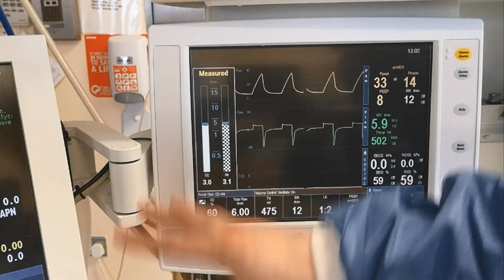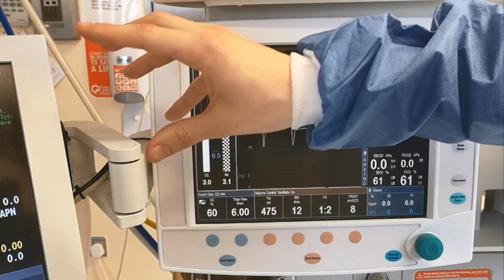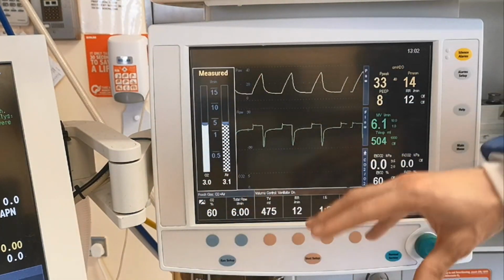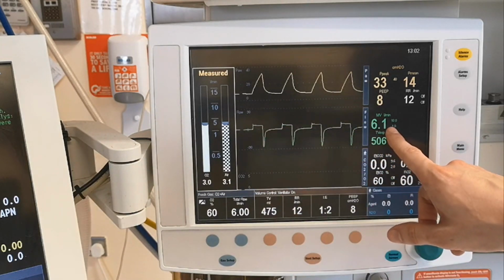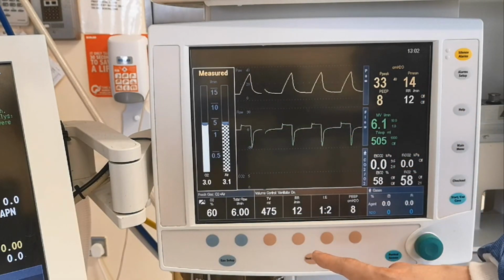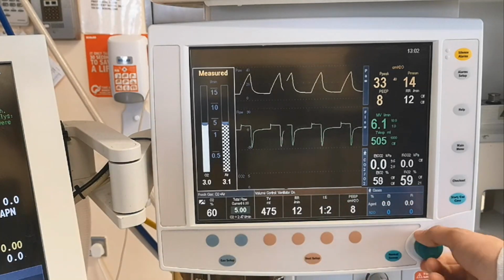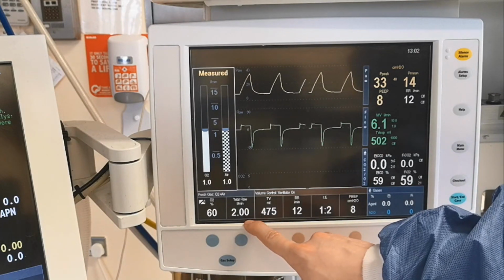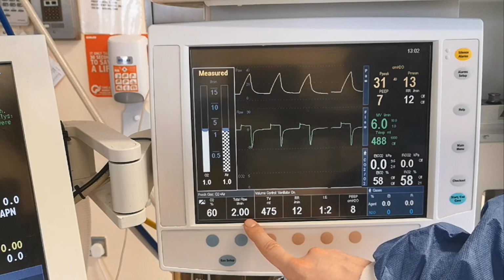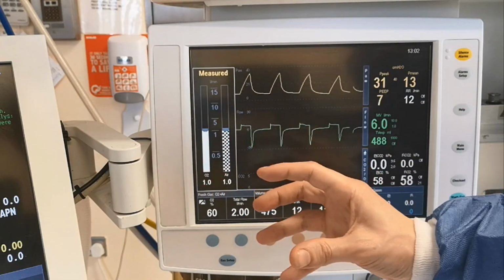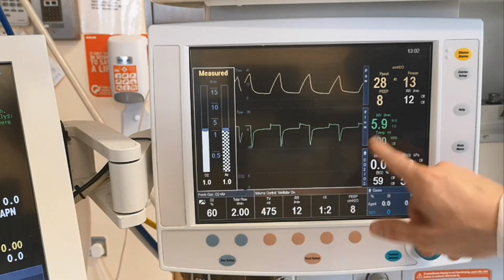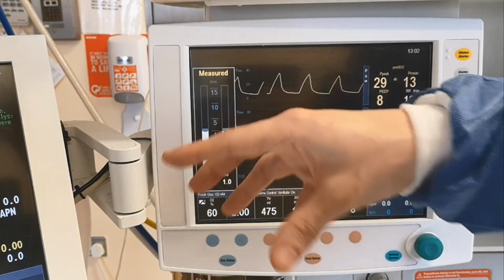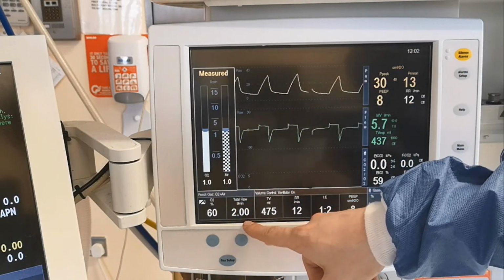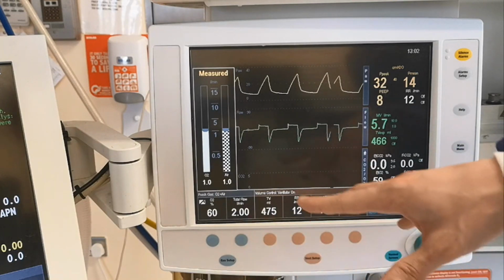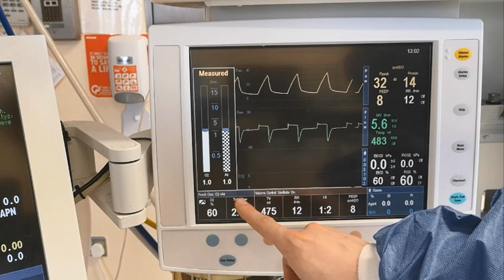This means that the patient is breathing always fresh air. The air is coming from the wall, air and oxygen come here, 6 liters every minute, and the patient is breathing in and out 6 liters per minute. Now, if I want, I can reduce the total flow here to 2, for example. This means that every minute we are getting 2 liters of fresh air from the wall that are going to be mixed with 4 liters in the circuit, because then the patient is rebreathing his own air, to which every minute 2 liters gets added. So the patient is rebreathing 4 liters, and every minute there are 2 liters of fresh gas.